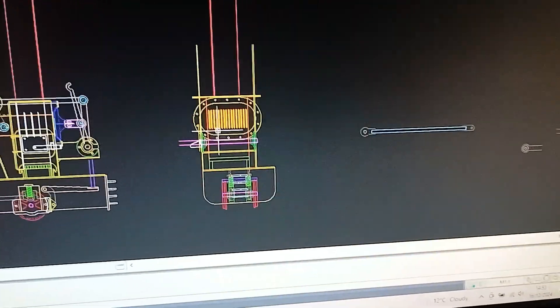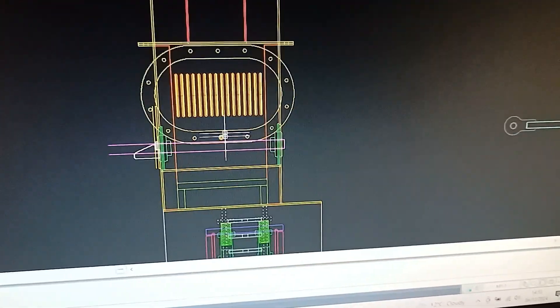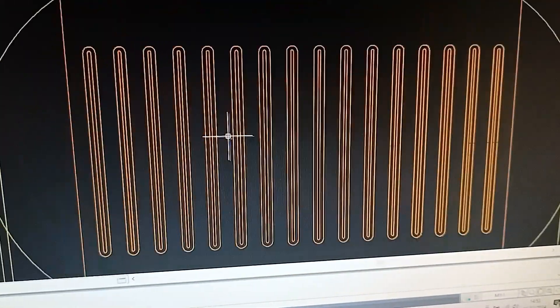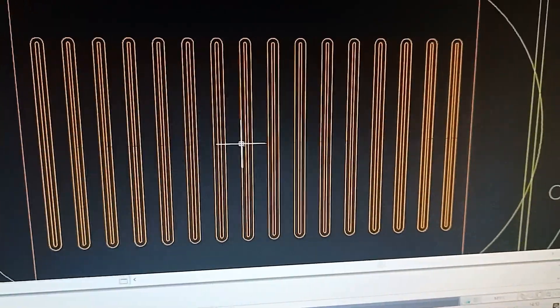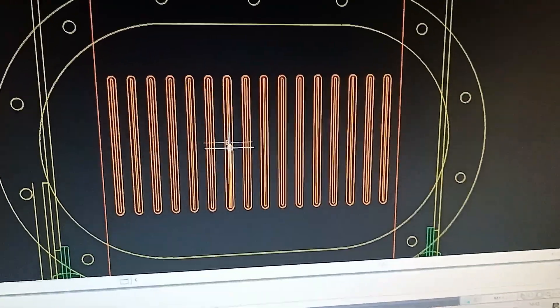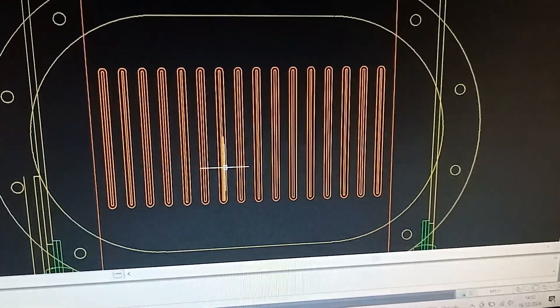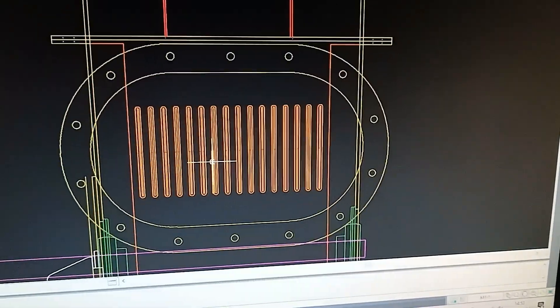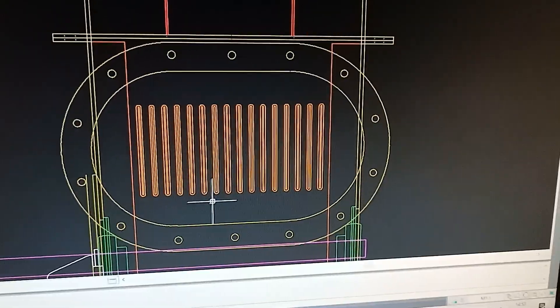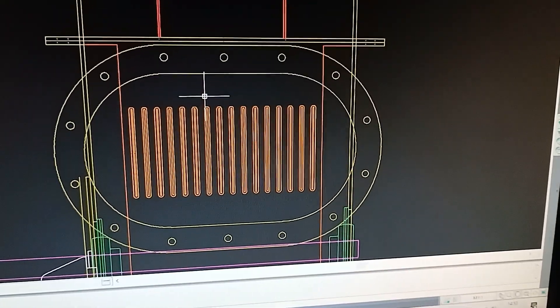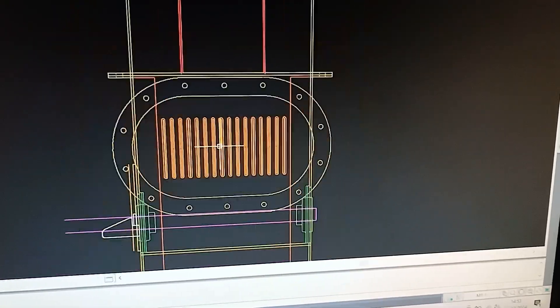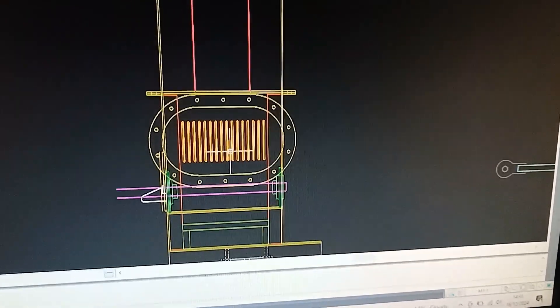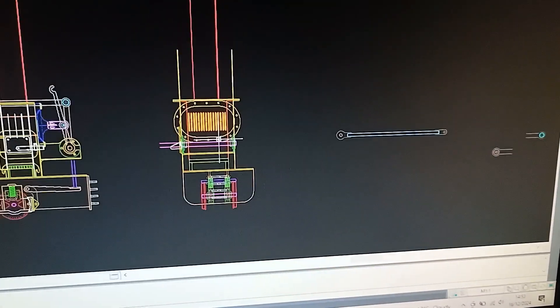So here's the end-on view. You can see all the tubes. This is a flattened tube to create a nice small air gap to hopefully get the maximum heat transfer from the flue gases passing outside of the tubes to the working fluid, which is air in this case, within the tubes.